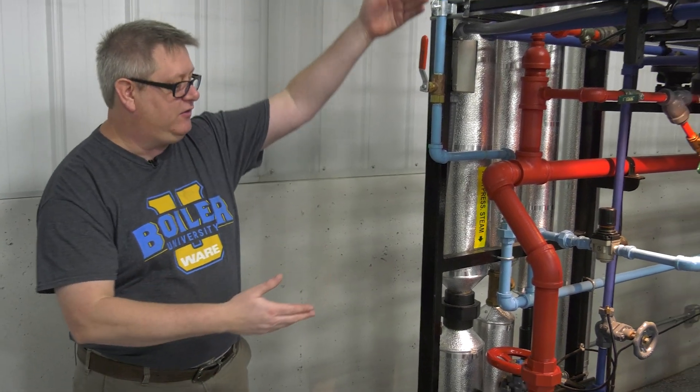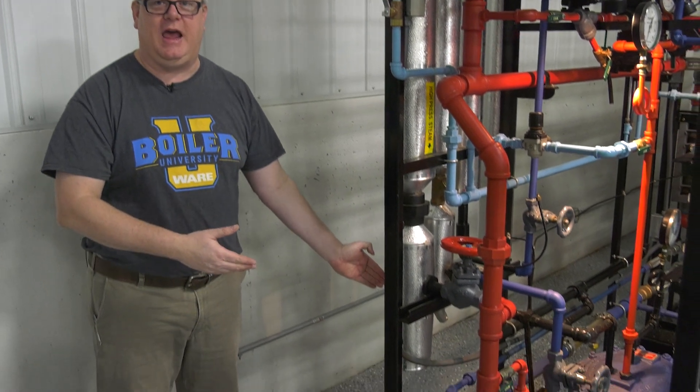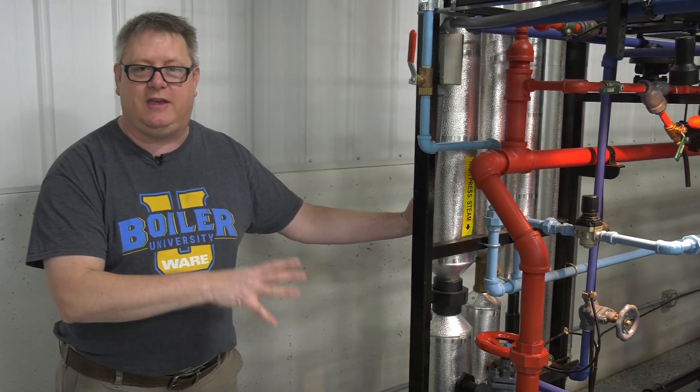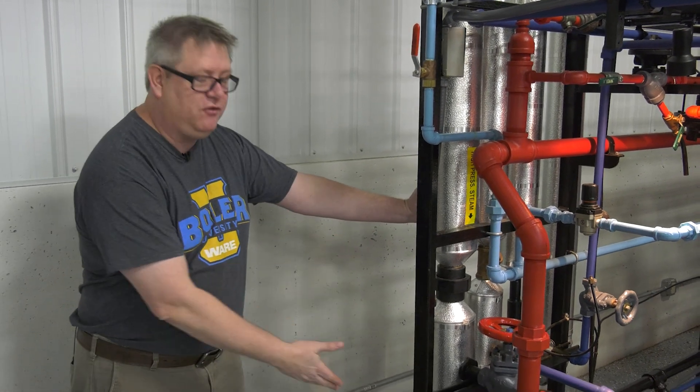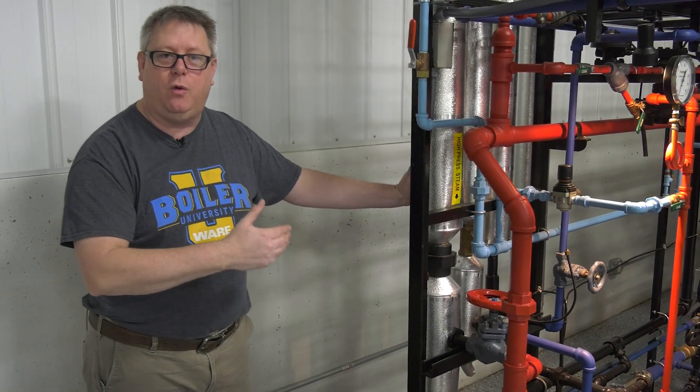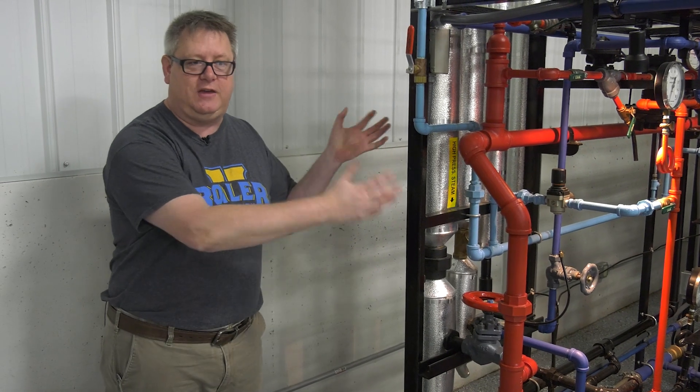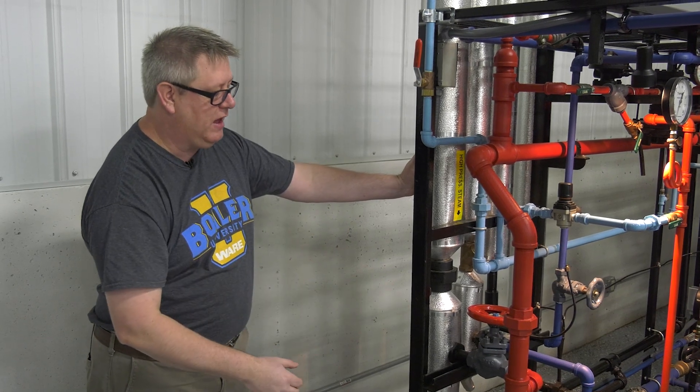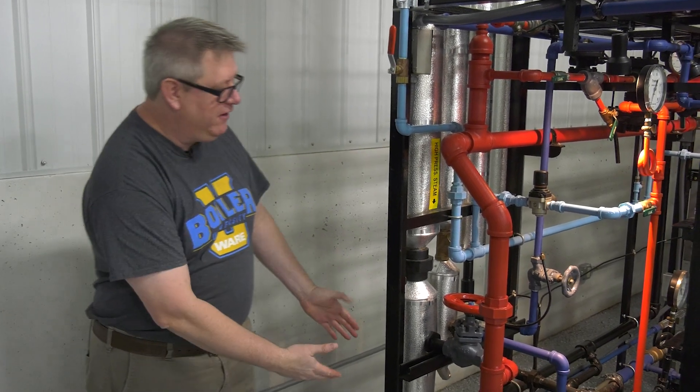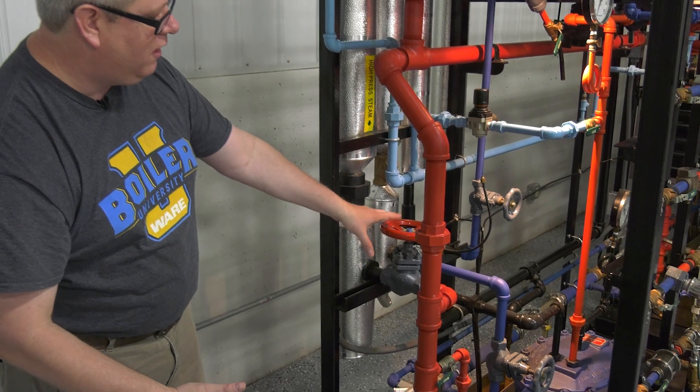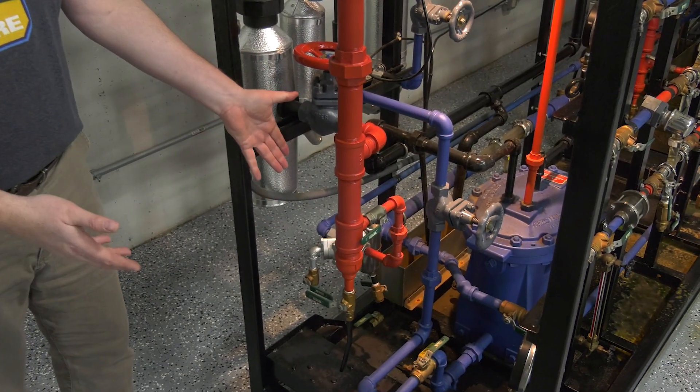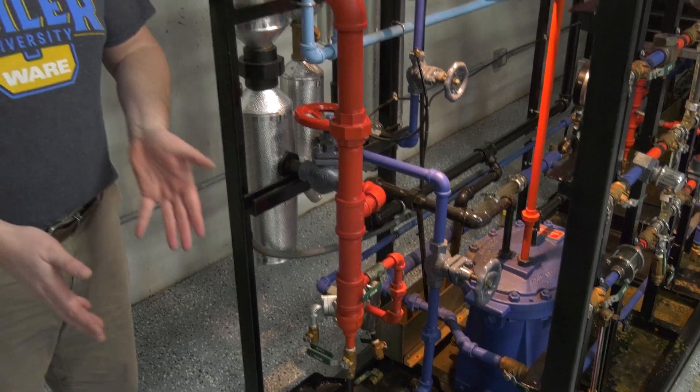Right here we've got a steam main dropping down to our trap demonstration skid, and this is a perfect location for a drip leg because we don't want to pull a lot of condensate into this skid. What we have here is our valve to control the steam going in and a section of pipe that goes down, and that is the drip leg.